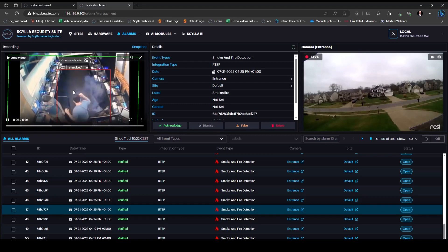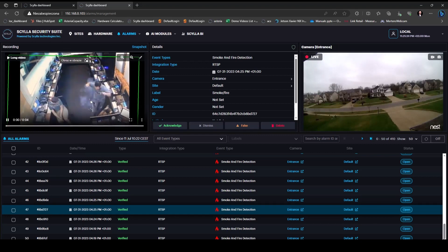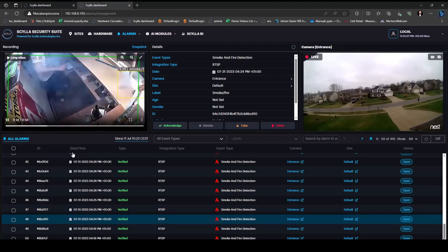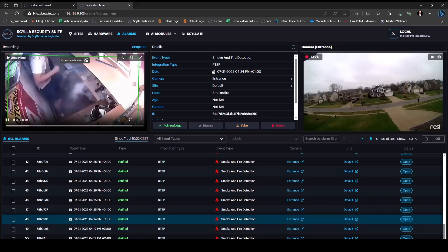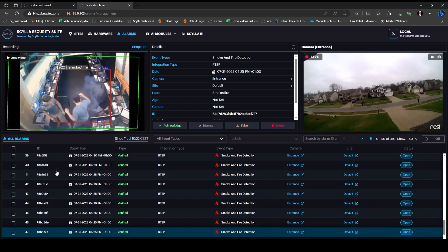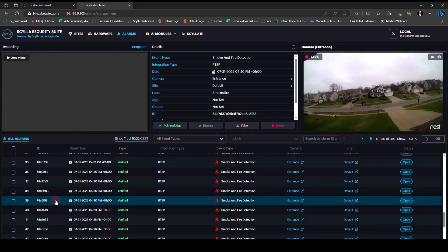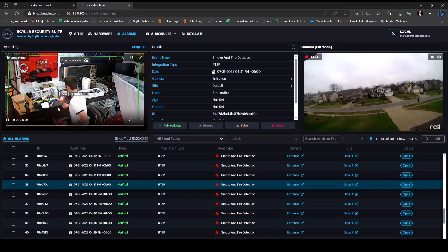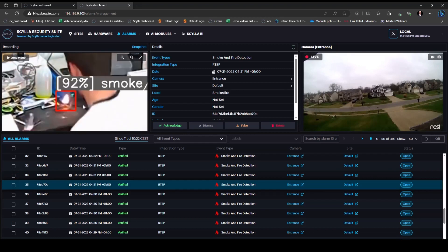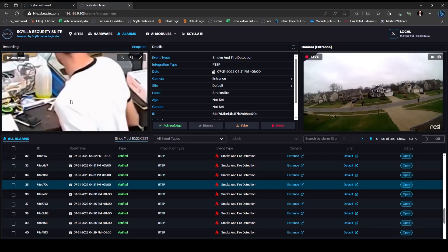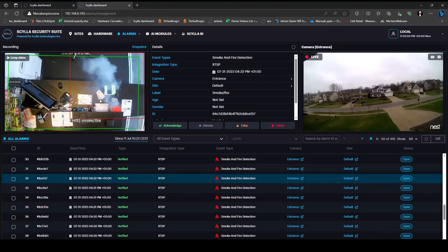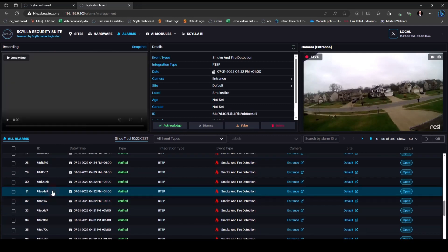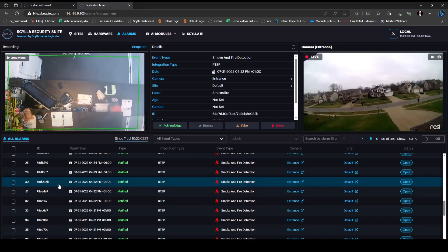Here we have the shaking video — somebody recording using their cell phone, recording the screen from the monitor. The smoke is actually blue, not white, and still we have no problem detecting it. Or here — the top view of the camera — we have fire detection. Let's see again: footage from the shop, detection. This is again the top view — they require 600 pixels to detect the fire; here it's maybe around 150 pixels — still no problem with detection. Top view of the cell phone — no problem. That's how we benchmark the solution.